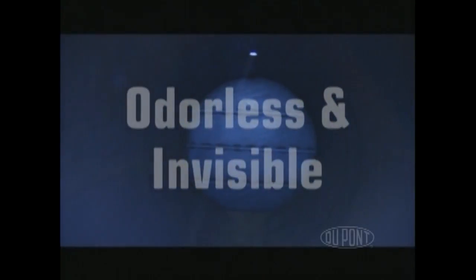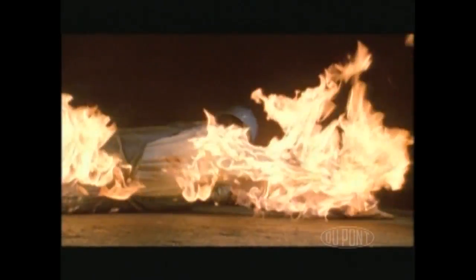Combustible gases create a threat of fire or explosion. These gases are often odorless and invisible, and if the concentration of a flammable gas is high enough, even a tiny spark can cause a catastrophic explosion. Flammable gases are second in the testing order because the threat of fire or explosion is more immediate and more life-threatening than exposure to toxic vapors.